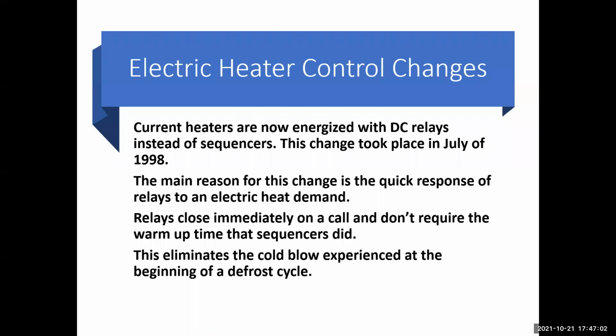Electric heat control changes. Current heaters are now energized with DC relays instead of sequencers. This took place in July of 1998, so it's been a while. The main reason for this change is a quick response relay to the electric heat demand. Relays close immediately on a call and don't require a warm-up time like the sequencers did. This eliminates cold blow experienced at the beginning of the defrost cycle.